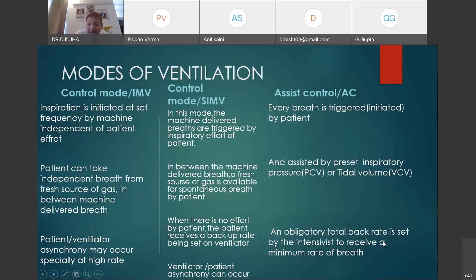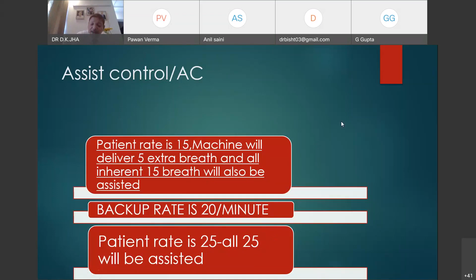See, if you have set in AC mode a backup rate of 20 per minute and the patient is able to take only 15 breaths per minute, so patient rate is 15, then what will be? Machine will deliver 5 extra breaths because we have set 20 breaths. So 5 plus 15 is 20. So machine will deliver 5 extra breaths and all 15 breaths of the patient will also be supported, assisted by the machine. But if the patient is breathing at a rate higher than we have set, we have set 20 and patient is taking 25, then what will be? All 25 breaths will be assisted by the machine. This is the beauty of AC, assist control mode of ventilation, my dear resident. This is a very beautiful mode of ventilation.